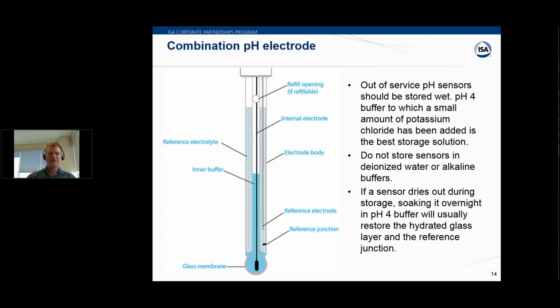So here's the combination electrode. You can see that we have all the elements. We have the refill opening, we have the reference junction going down the right, and then we have the inner buffer and the glass membrane down at the very bottom. Now the shape of that membrane can be a wide range of shapes depending on what you're trying to measure, and in some cases it can almost be like a spear for measuring the pH of semi-solids, so that it's made to be more durable like that.